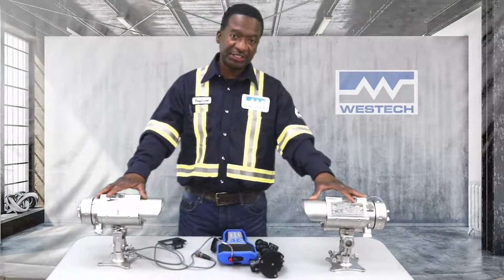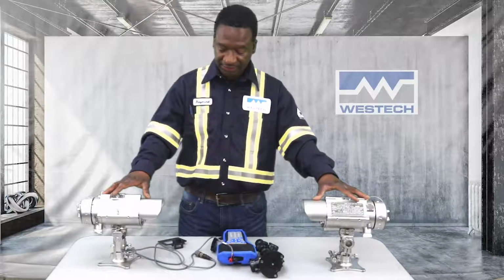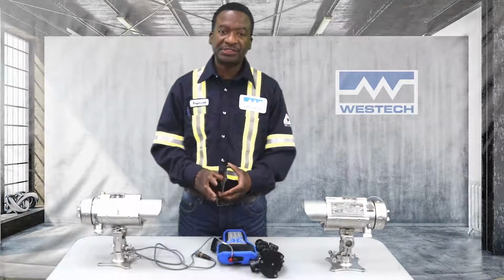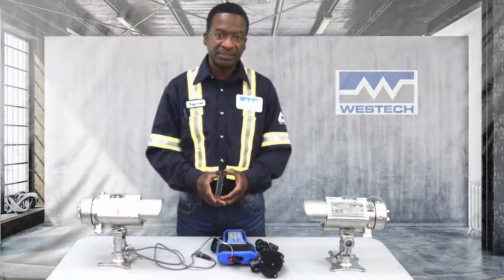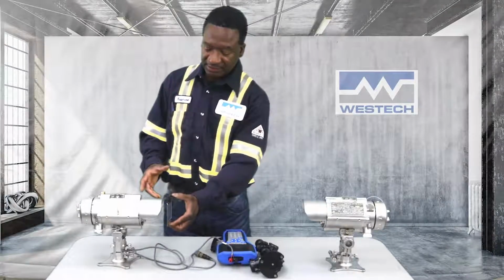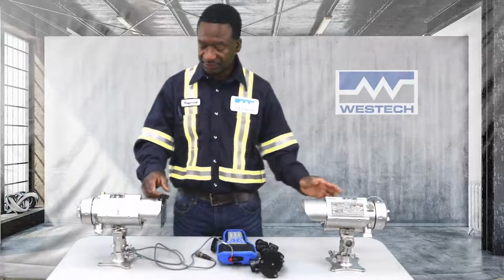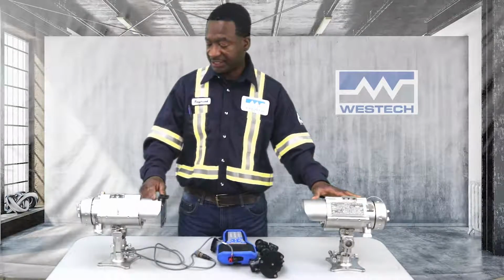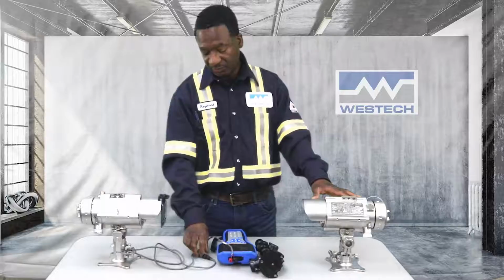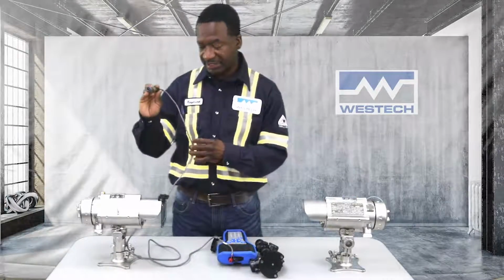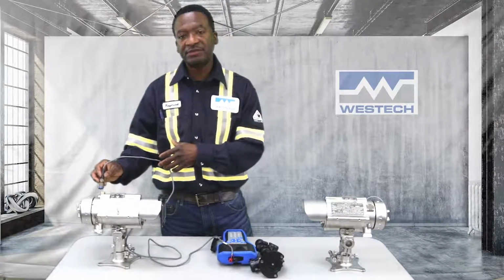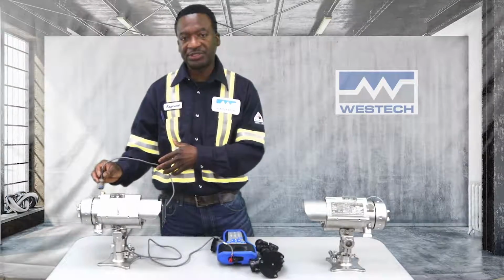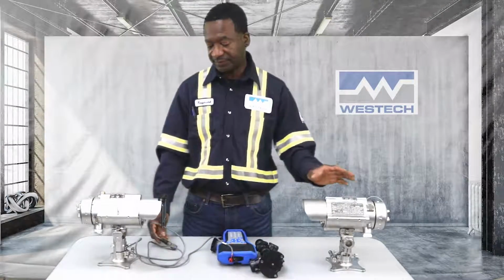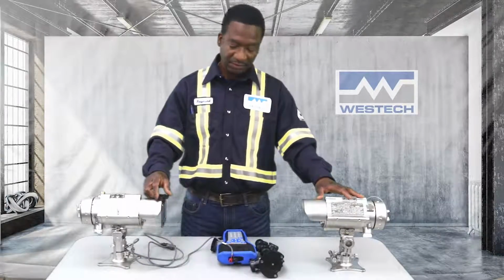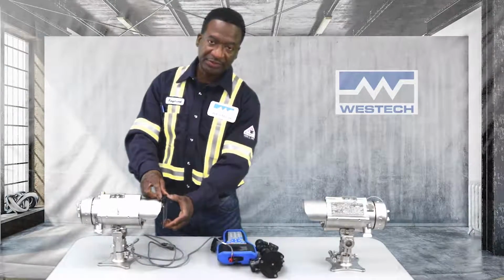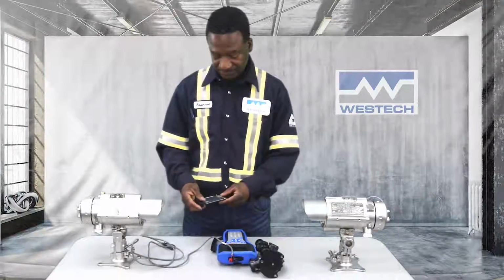Once an alignment has been achieved and the zero calibration has been successfully done, it becomes necessary to simulate a response from the detection system. This can be done by fitting a supplied filter onto the face of the receiver and then taking the output signal with your HART communicator with the supplied cable, or watching the 4 to 20 milliamp signal back at your PLC. There are two supplied filters in the LEL kit. One is for a low response and the other is for a high response.